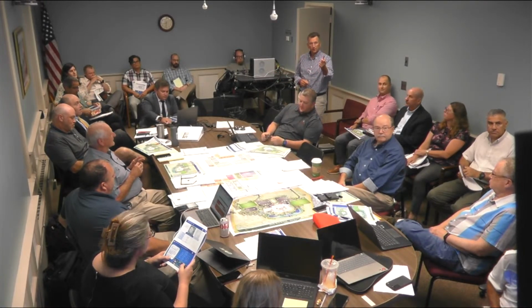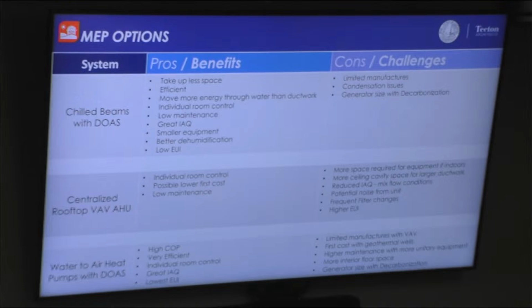And next, here's our system types: chill beam, centralized rooftop, or indoor air handler, or water to air heat pumps. Some pros and cons versus the two. So chill beams, they take up less space. All the chill beams are located in the ceiling. Very short height, so you don't need big ceiling cavities.